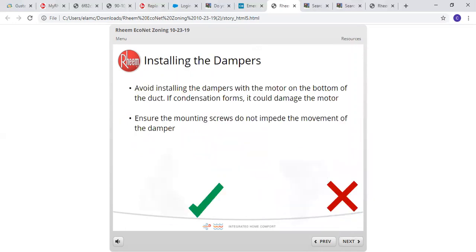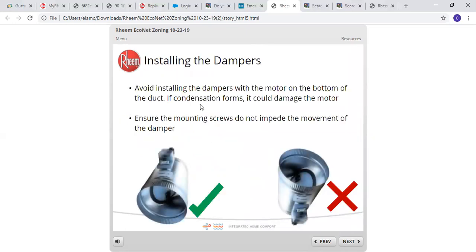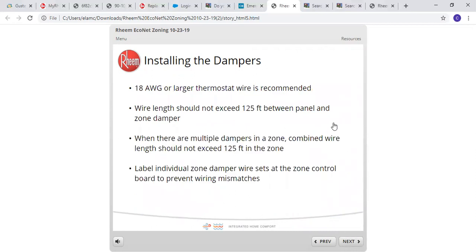And then installing the various dampers. Avoid installing the dampers with the motor on the bottom. If condensation forms, it could damage the motor. Ensure the mounting screws do not impede the movement of the damper. I've had that happen to me a few times, and that's always a bear once it's installed. So as you can see here, they're recommending that you mount the motor up on top, not on the bottom.